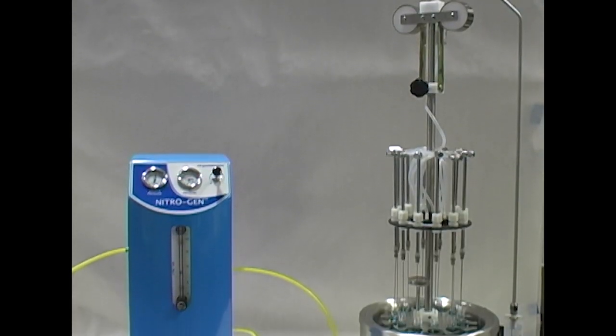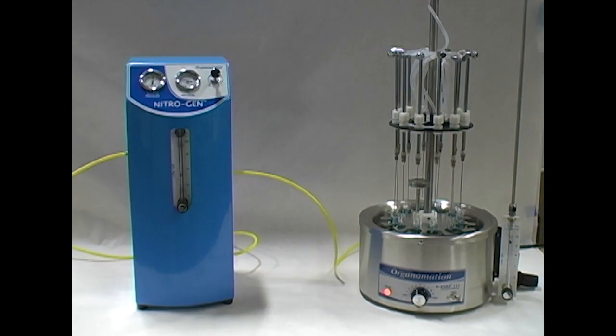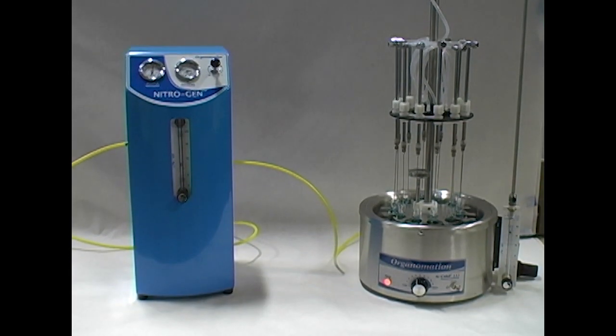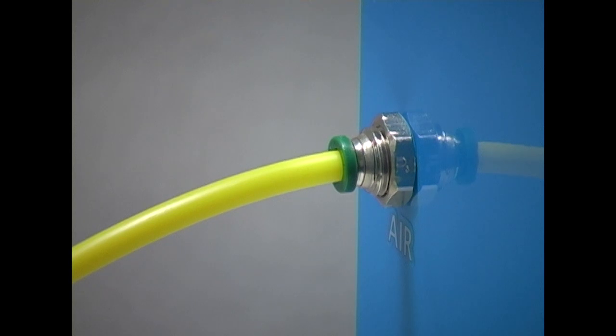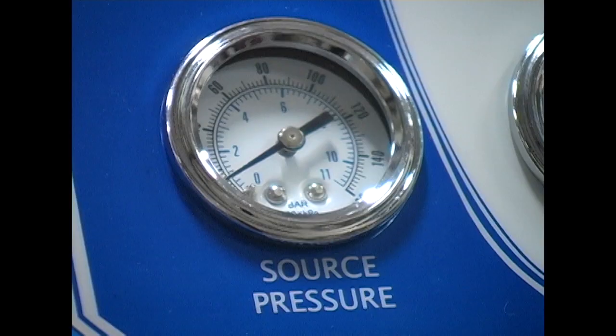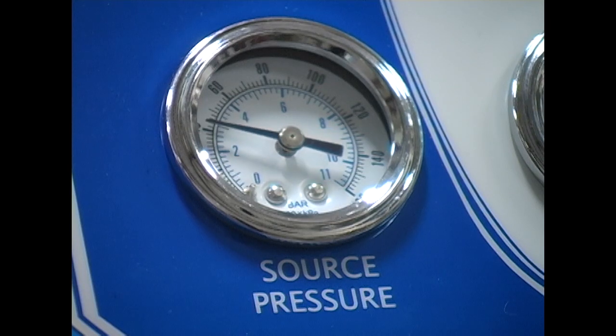It is an ideal choice for any lab looking for a low-cost solution to integrate with their clean air line. It's portable and lightweight, working with a lab's existing compressed air supply to produce nitrogen gas. No electricity is required as it runs off of the pressure provided by the compressed air source.